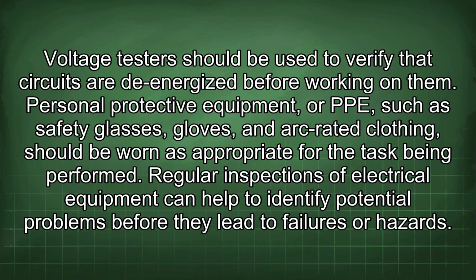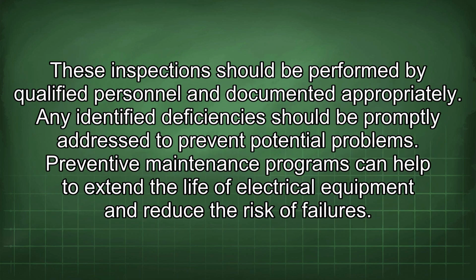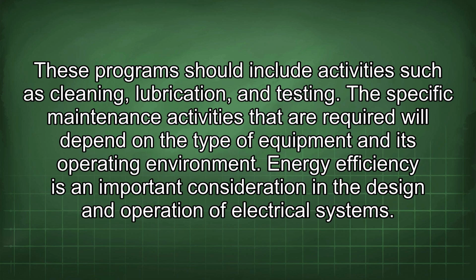Regular inspections of electrical equipment can help to identify potential problems before they lead to failures or hazards. These inspections should be performed by qualified personnel and documented appropriately. Any identified deficiencies should be promptly addressed to prevent potential problems. Preventive maintenance programs can help to extend the life of electrical equipment and reduce the risk of failures. These programs should include activities such as cleaning, lubrication, and testing. The specific maintenance activities that are required will depend on the type of equipment and its operating environment.